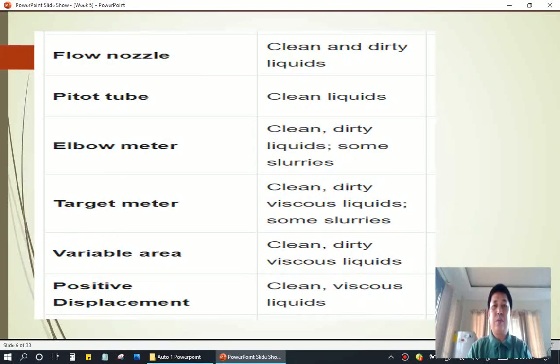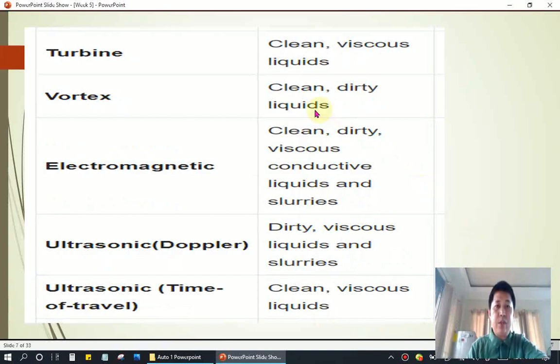Flow nozzle type. So this is used for clean and dirty liquids. Pitot tube type, for clean liquids only. Elbow meter type. Later on, I will show you the image of these types of flow meters. So clean, dirty liquids, and some slurries. We have here target meter, intended for clean, dirty, viscous liquids, and some slurries. Variable area, clean, dirty, and viscous liquids. Positive displacement, clean, viscous liquids. Turbine type, clean and viscous liquids. Vortex, clean and dirty liquids. Electromagnetic, clean, dirty, viscous, conductive liquids and slurries.